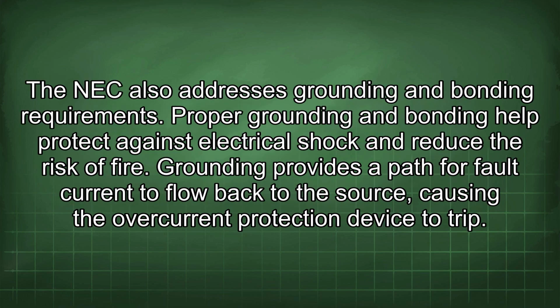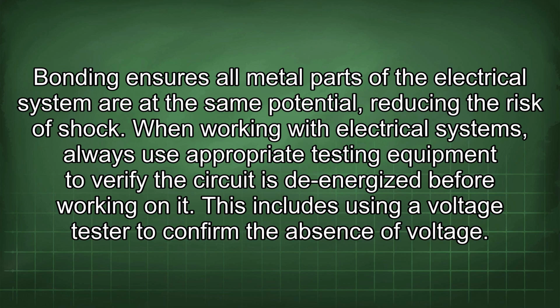The NEC also addresses grounding and bonding requirements. Proper grounding and bonding help protect against electrical shock and reduce the risk of fire. Grounding provides a path for fault current to flow back to the source, causing the overcurrent protection device to trip. Bonding ensures all metal parts of the electrical system are at the same potential, reducing the risk of shock.